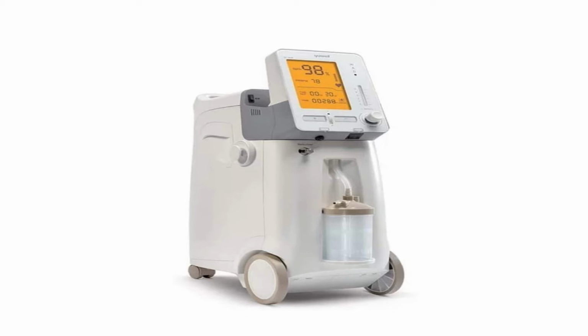A pressure valve in concentrators helps regulate supply ranging from 1 to 10 liters per minute. According to a 2015 report by the WHO, concentrators are designed for continuous operation and can produce oxygen 24 hours a day, 7 days a week for up to 5 years or more.